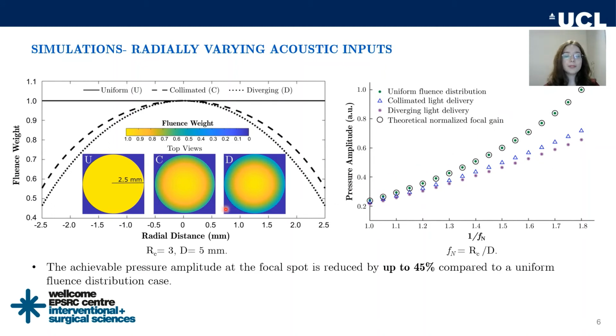Here you see an example scenario for a transducer which we are looking at from the top, and as can be seen on the left-hand side of the inset, ideally each part of the transducer should receive a uniform light intensity. However, in reality, the intensity at the edge of a transducer could be as low as half of the intensity at the center. So due to these non-uniformities in the light intensity, we estimated that the achievable pressure amplitude at the focal spot is reduced by up to 45% compared to a uniform light intensity case. This reduction could be a potential drawback towards clinical translation.